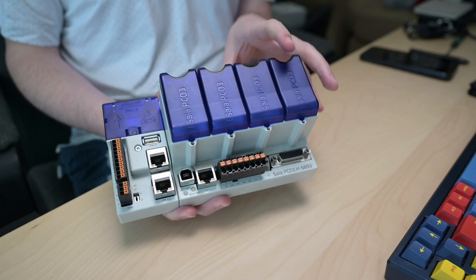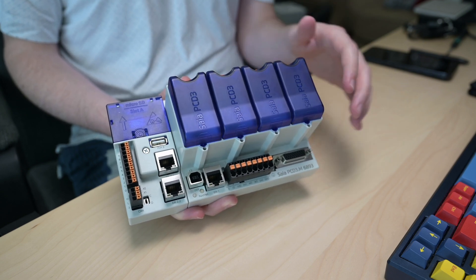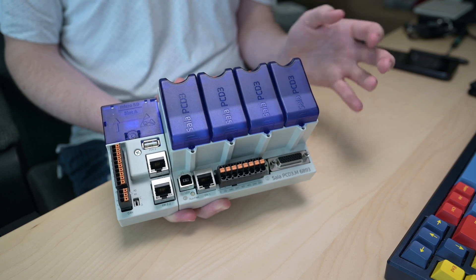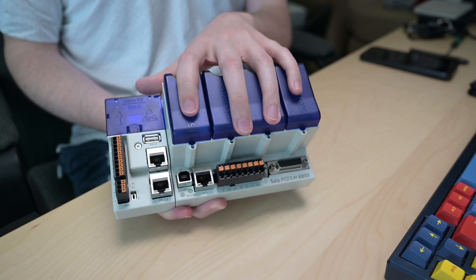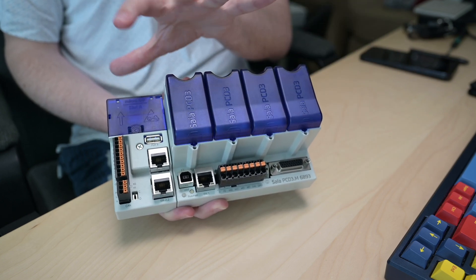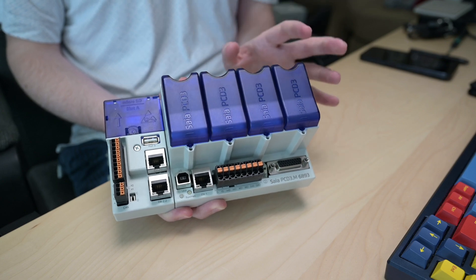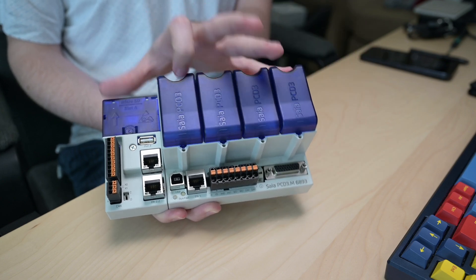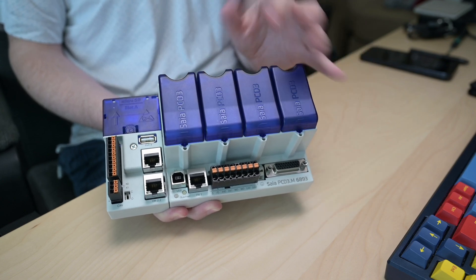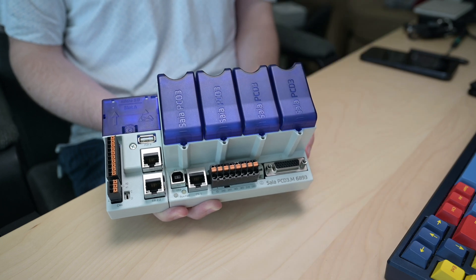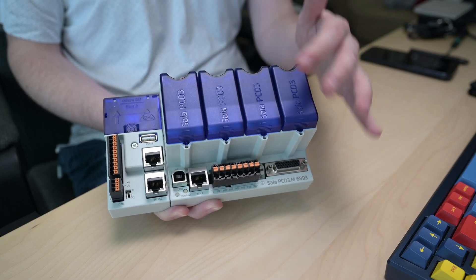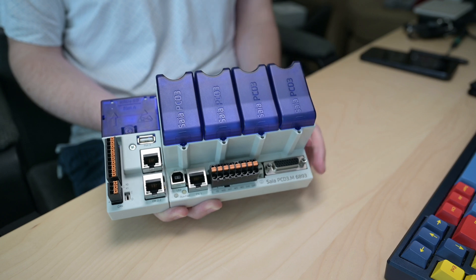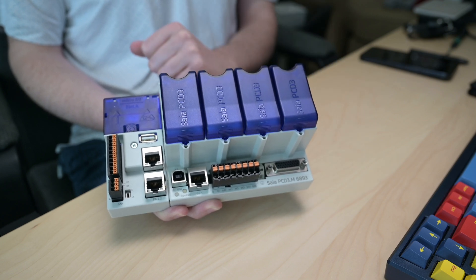That is key if you want to do actual redundancy, because when you're doing a redundant controller or redundant system, you don't want your IO to be on the device that you think could potentially fail, right? So you would have two of these controllers with no IO at all. All of your IO then would be moved out to an IP-based housing that has all of the IO that you're talking to from your controllers.